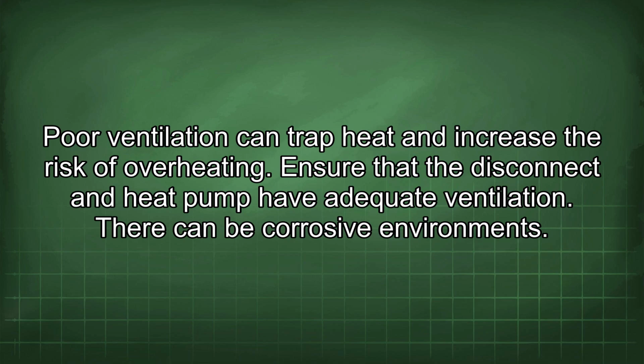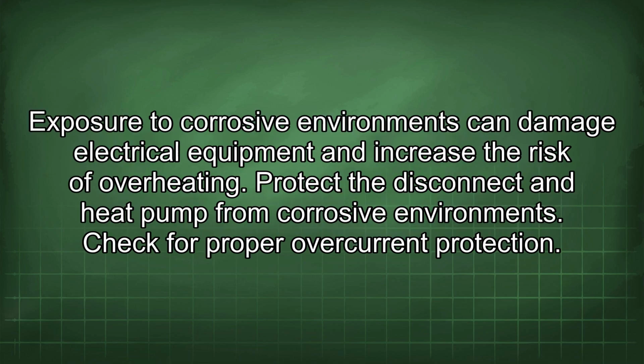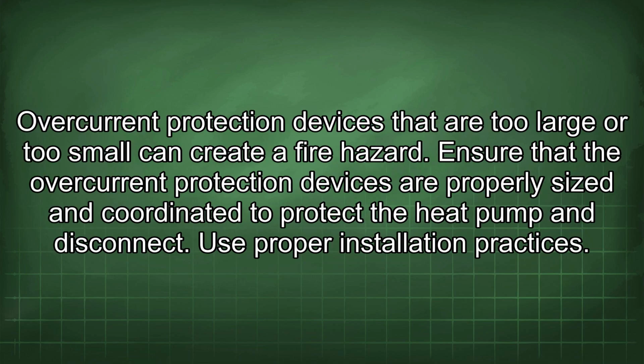There can be corrosive environments. Exposure to corrosive environments can damage electrical equipment and increase the risk of overheating. Protect the disconnect and heat pump from corrosive environments. Check for proper overcurrent protection. Overcurrent protection devices that are too large or too small can create a fire hazard. Ensure that the overcurrent protection devices are properly sized and coordinated to protect the heat pump and disconnect.